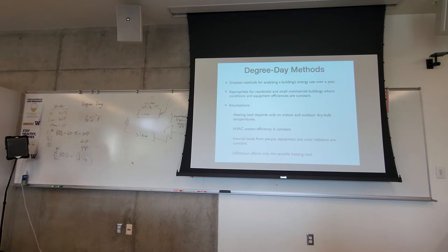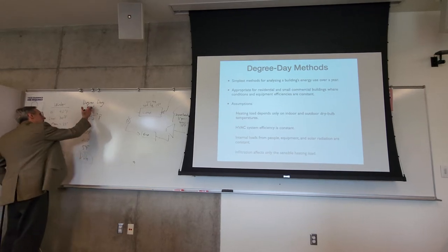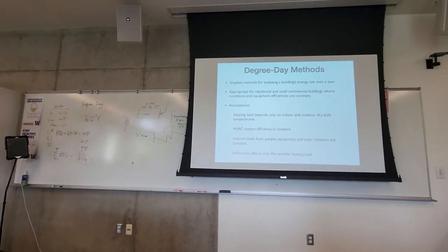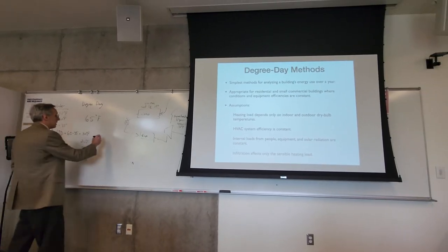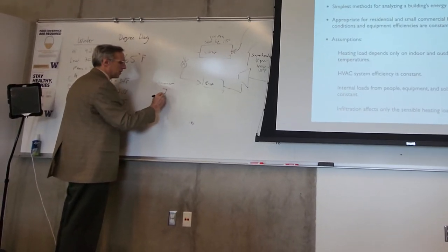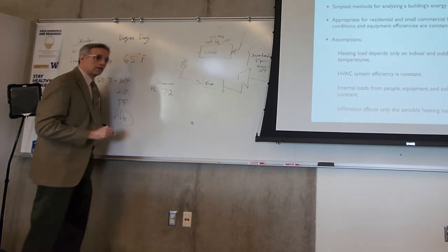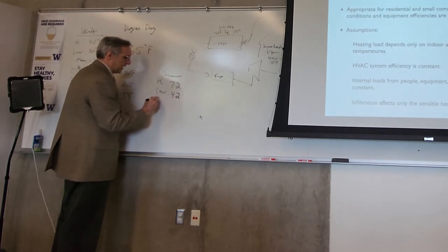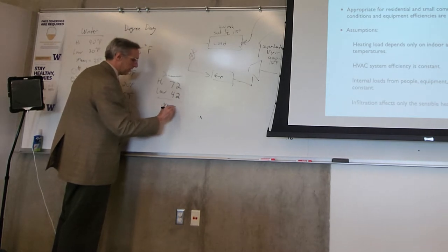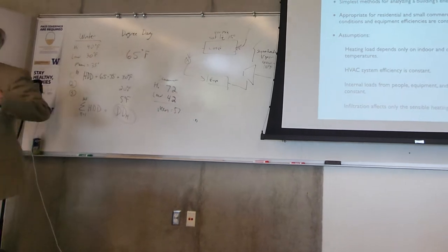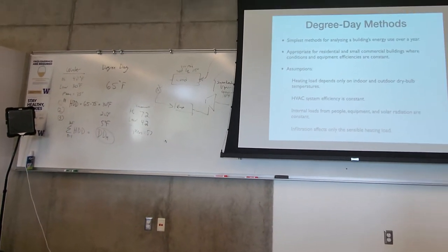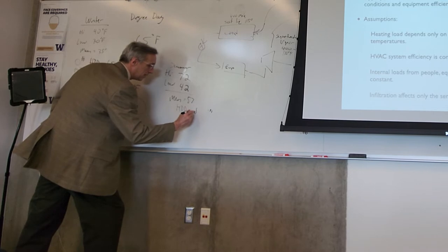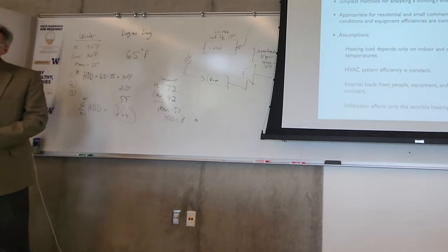And then there's a similar one for summer, where, of course, you're going to be above. So you're looking at the increments above 65 degrees, and that's when you're assumed to need cooling. Okay, so I don't know what it was yesterday. It was probably 72 for the high. And the lowest, it was pretty cool. It was probably 42, something like that. So we probably still needed heat that day. That probably would have classified as a winter day, because we're below 65. So the number of heating degree days would be 8. It seems weird that yesterday would have been a heating day.